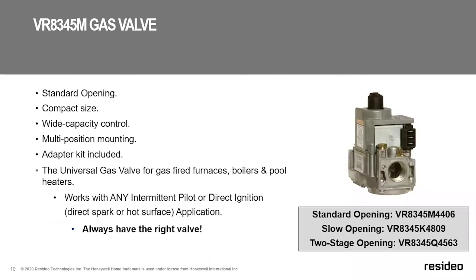Another very important piece of the universal stocking inventory that you should have on your trucks is our VR8345M universal gas valve. One gas valve on your truck covers both 1/2" and 3/4" installations. It comes with the appropriate fittings, so you can use it on 1/2" or 3/4". It's very compact in size, but it actually fits. It replaces a lot of existing valves without having to do any repiping.